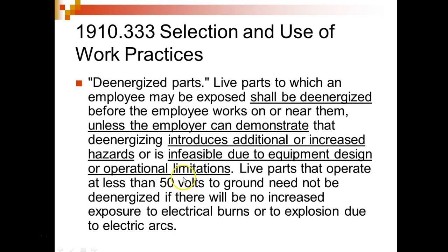So what they've established is 50 volts. Anything above 50 volts, we're going to have to start considering. When I work on it, I'm going to have to do what? I'm going to have to de-energize it. At 50 volts, it all depends on different things. That makes sense? So legally, our system, of course, this is a training system. Our systems here will operate on 24 volts DC. So that means we could operate on these, but we're not. So we're going to treat this like it's a high lethal voltage just to get you used to doing this. Are you okay?